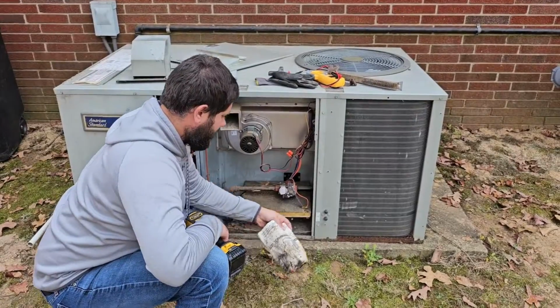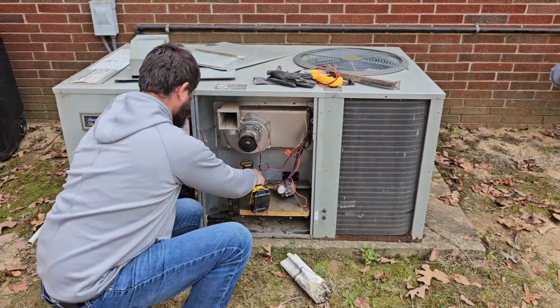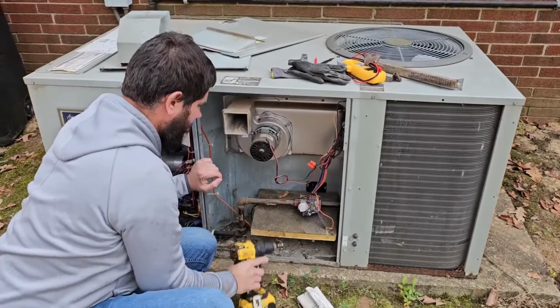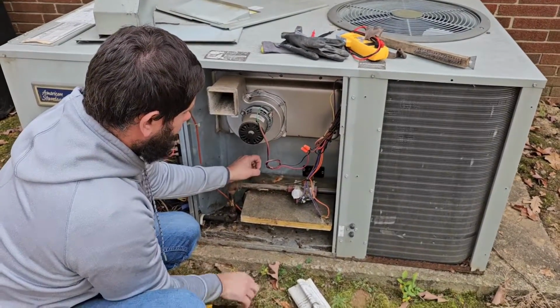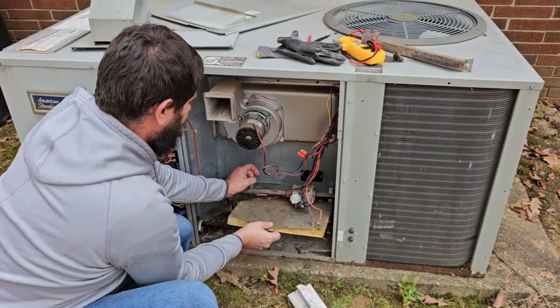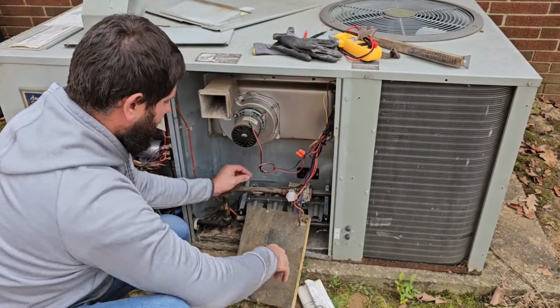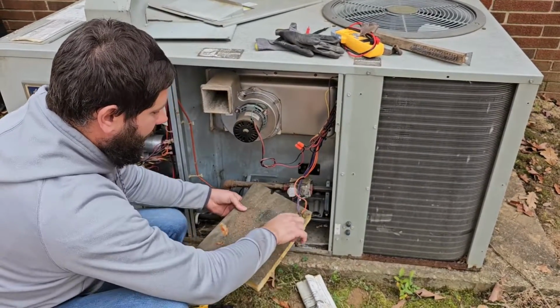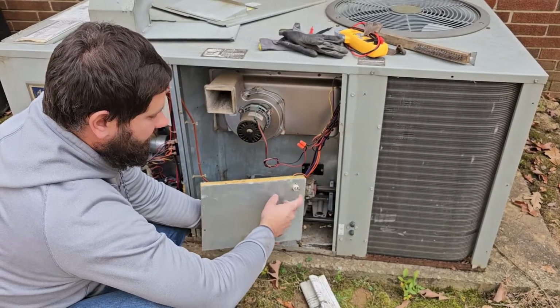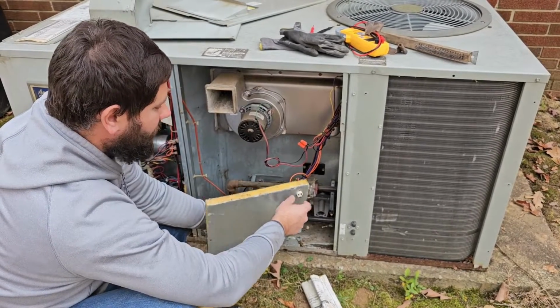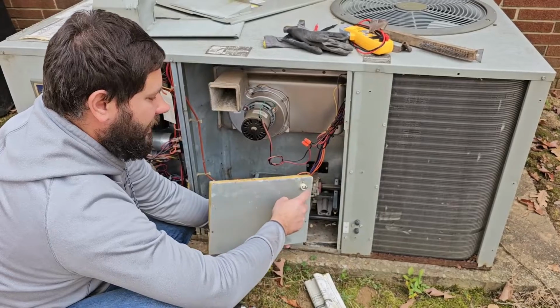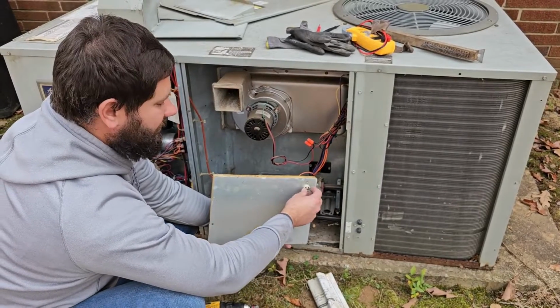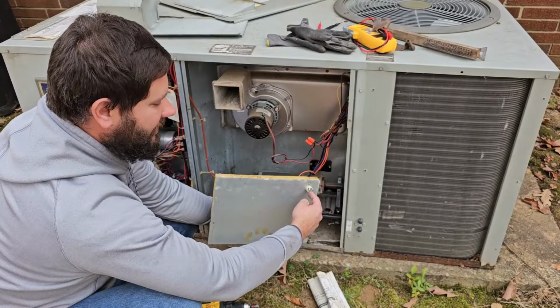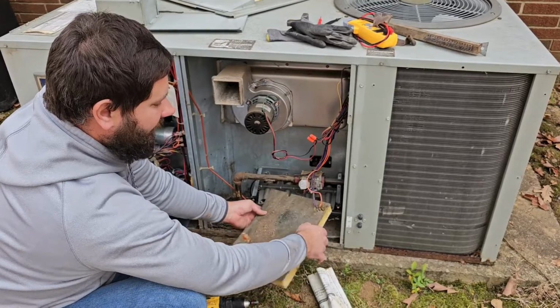All right, so we've got these three panels off right here. And I always like to watch the flame light. So I take this cover off. That way I can see the burners. What we've got right here on this panel is a rollout switch. You can see right there, we've got our little fusible link. Whenever the flame is rolling out, it burns that. And then it disconnects the two wires that connect to it, right?